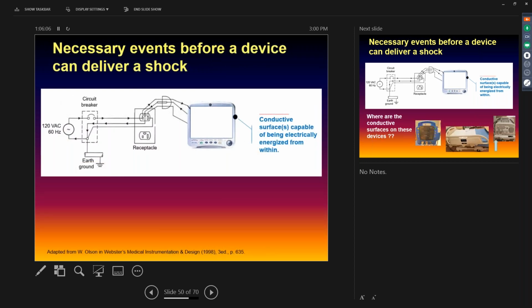But this is where I ultimately wanted to get to. This is the whole point of all of this ramble, to get to why we have to have certain things in place before we're going to shock anybody. Whether it be a macro shock, arm-to-arm external, or a micro shock through an indwelling catheter, there are 5 things that all have to be present in order for us to have any risk at all. First thing, we have to have some conductive case on our devices that is capable of being energized electrically from the inside. This automatically throws out anything that's double insulated, either UL double insulated or effectively double insulated - you've got to have a conductive case that can be energized from the inside.